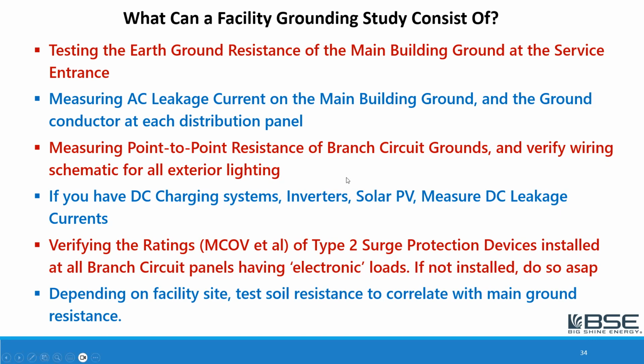Another important thing to do is point-to-point resistance testing of the branch circuit grounds. That verifies, for safety reasons especially, but also for the life of your electronic equipment, that you may have a great main building ground, but what if somewhere there's a break or a loose connection in the grounding circuit and you don't get a good ground from the equipment back to your main panel? Then if you have DC equipment, DC charging systems, battery chargers for forklifts, inverters, solar PV, you can also measure DC leakage current if you have the right type of clamp meter.